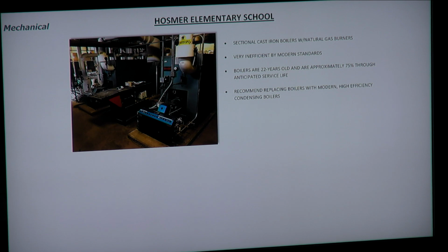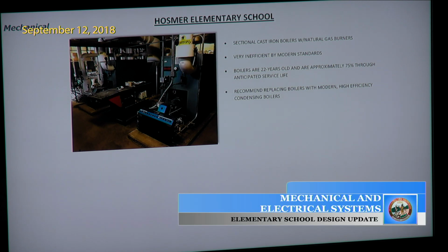Like the Hosmer boilers, these are outdated and coming up at the end of their service life. These are cast iron boilers that were only about 78 to 80% efficient when brand new. Now the efficiency based on age is down in the 60s and 70s. So we recommend having these boilers replaced. They're 22 years old, already 75% through their life, so this is something that should be considered on any project. However, the way the Hosmer plan is shaking out, we'll have a new boiler room in the new section of Hosmer, and we'd be piping back to the existing school anyway.